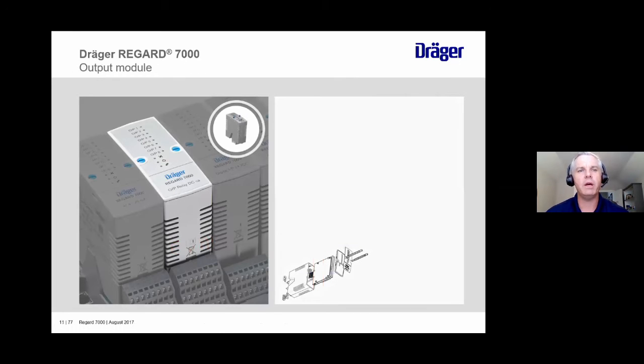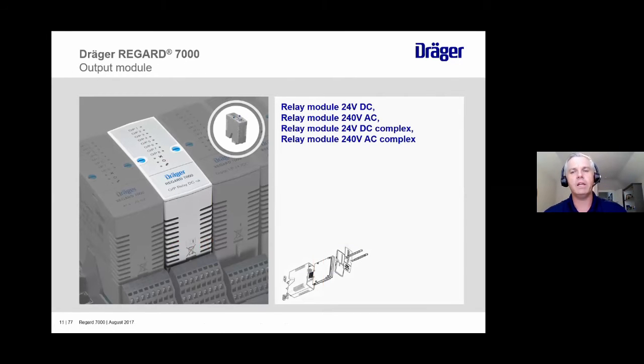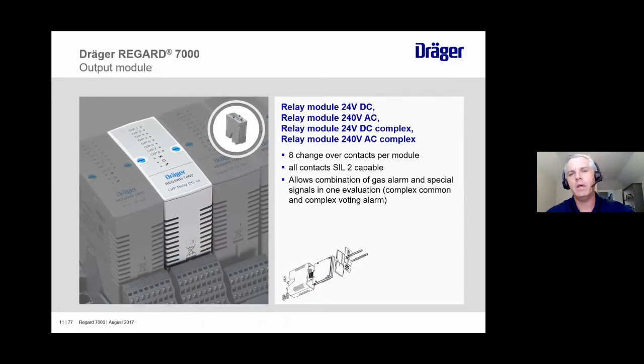So next I want to talk about the relay module. Like I mentioned, we have regular relay modules and complex relay modules. Each one of them has 8 change-over contacts per module. That means each module will have 8 different relay contacts that you can trip. All the contacts are SIL2 capable. It allows combination of gas alarm and special signals in one evaluation. And that's the big difference between the regular relay module and the complex.